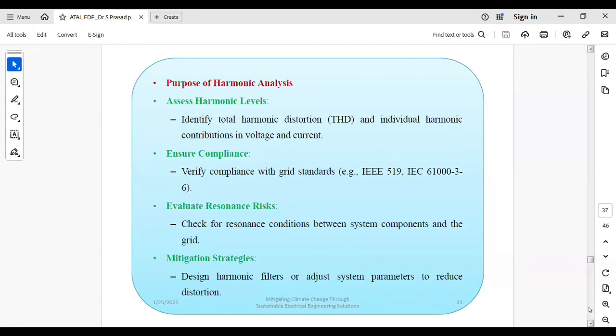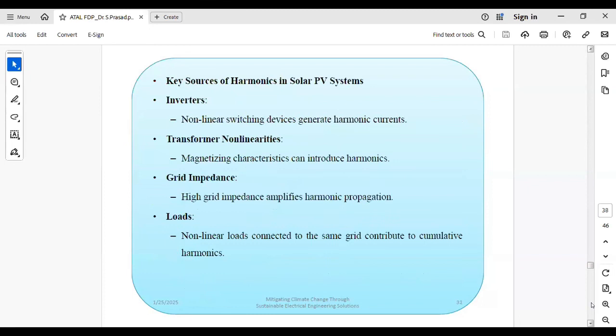So these are the things we need to follow, and we have to ensure that it is following the grid compliance and grid standards, IEEE 519, IEC 61000-3-6. They are the standards it has to satisfy. And how to mitigate the flicker effect and harmonics effect: by installing harmonic filters. Based upon the percentage of harmonics, you have to decide the size of the filter.